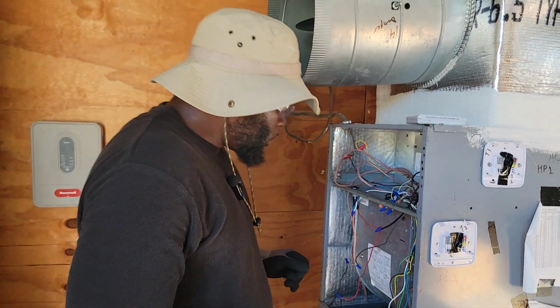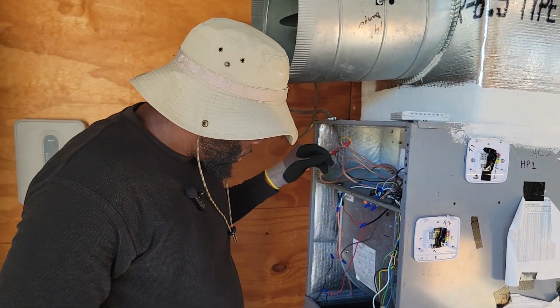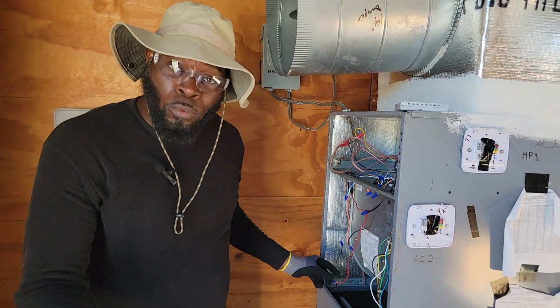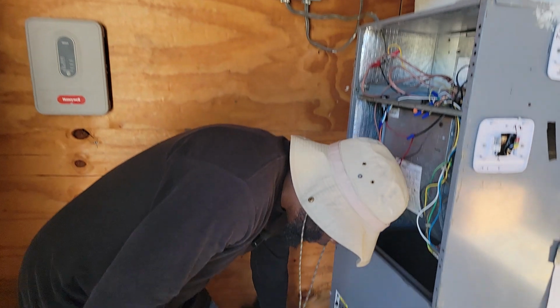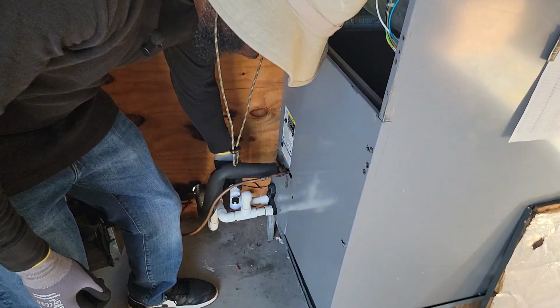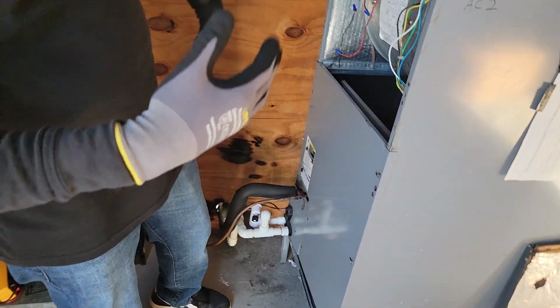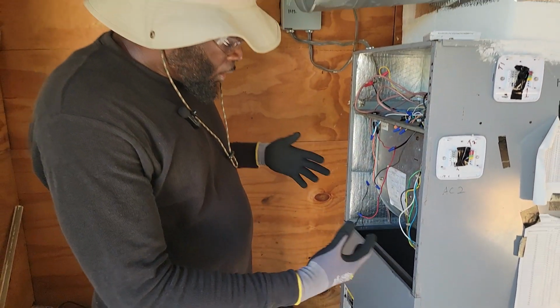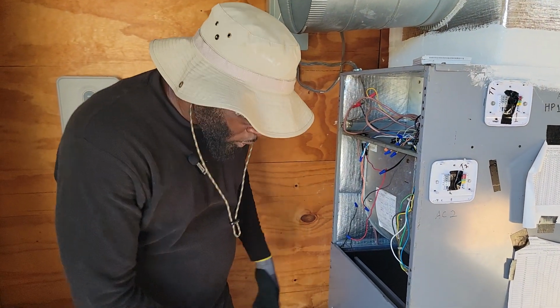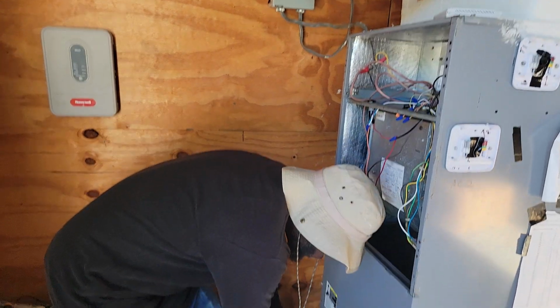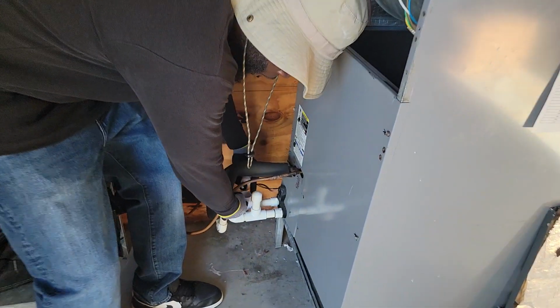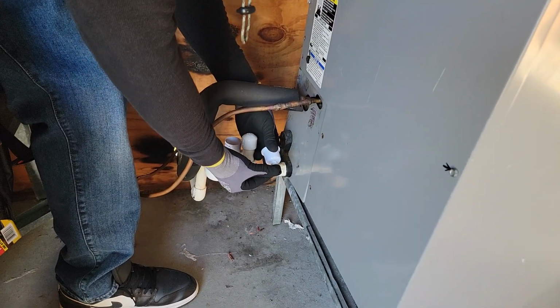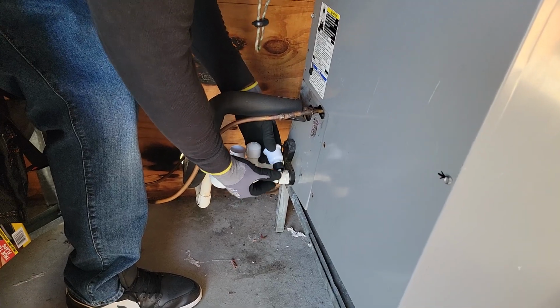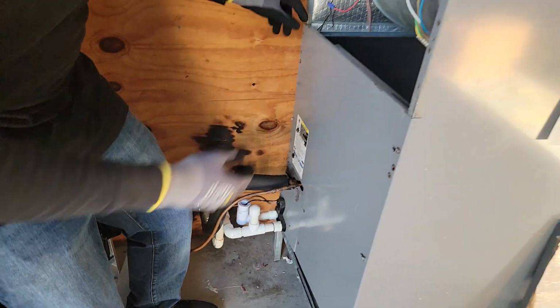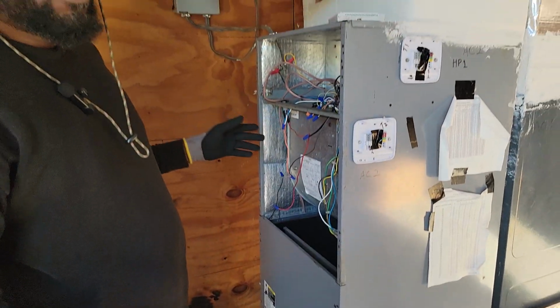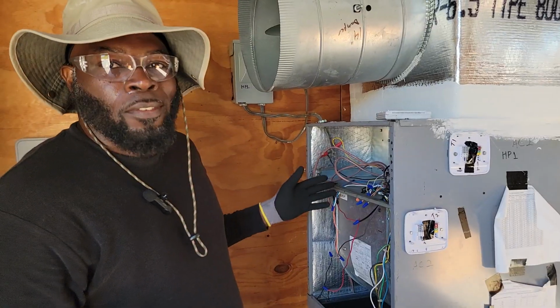Second of all, from your low voltage, you go down to something called a float switch. The reason for the float switch is just in case you have a clogged drain line or any kind of backup of water in the system. The water will rise in this pipe, and it will push this float switch up like this, and that will tell the entire system to shut off. Hey, I'm drowning. Shut off.